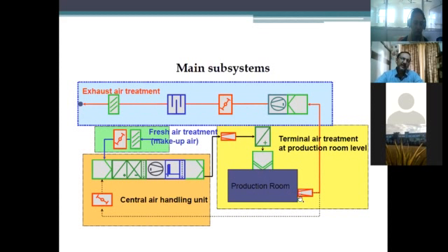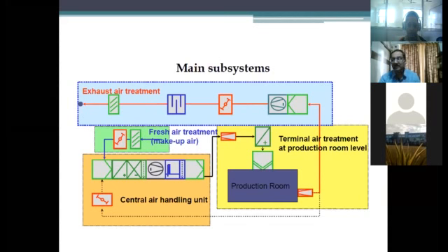And from there, this is the return air duct. It is going out. Exhaust air. This is the damper. This is the silencer, filter, and it goes out. This is a typical system where 100% exhaust is there. No recirculation is shown over here. Mind you, there are two types of AHUs. One in which there is recirculation of the treated air. Second one is where if you are using that area for manufacturing of beta-lactam antibiotics, or cancer drugs, then it is a mandatory requirement that 100% exhaust should be there.